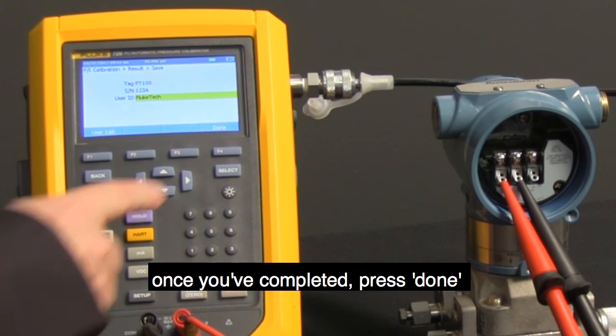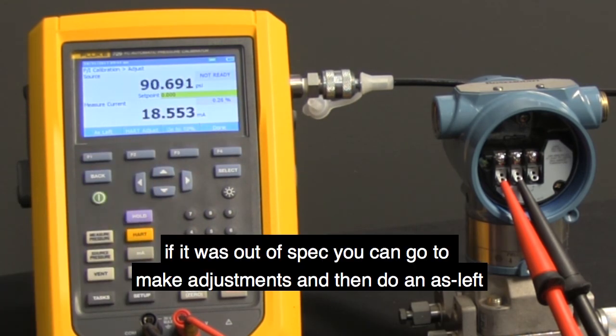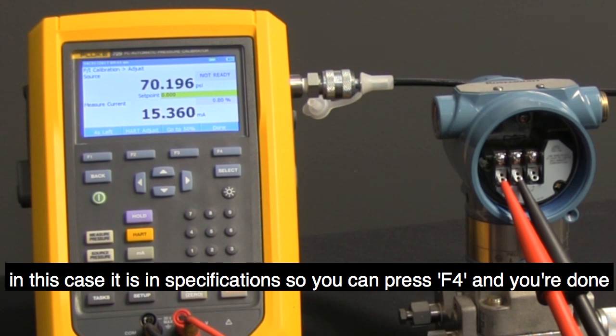Once you've completed, press done and now the calibration has been documented. If it was out of spec, you can go to make adjustments and then do an as left. In this case, it is in specification, so you can press F4 and you're done.